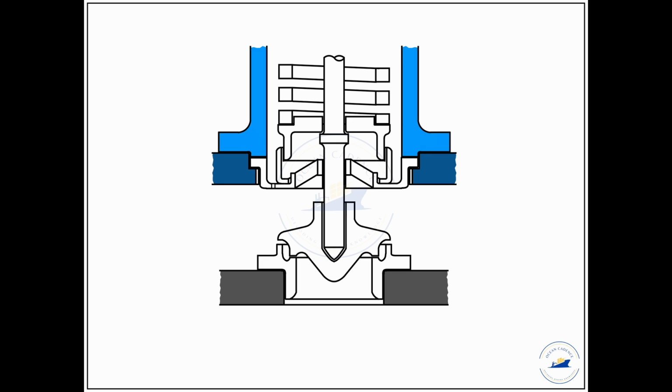As well, you can see the drain passages that are available, so obviously there will be drain channels leading to the lower drain side. These drain channels have to be clearly inspected and it has to be made sure that the channels are open and clear at all points of time so that any drained water can easily find its passage downstream and get drained.